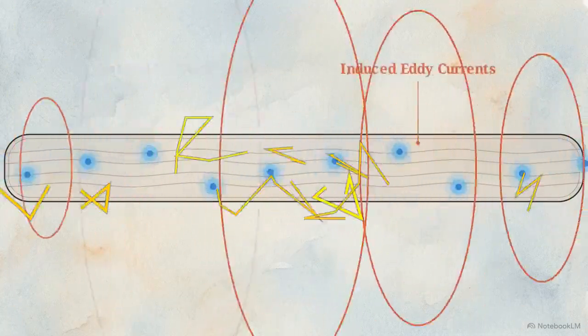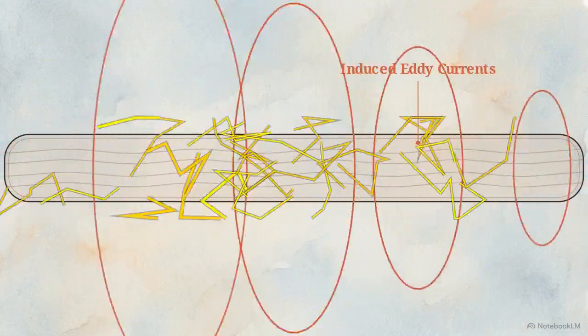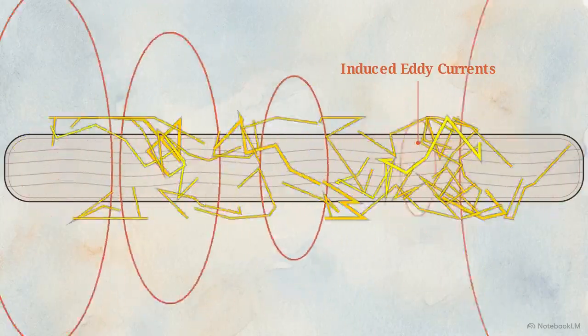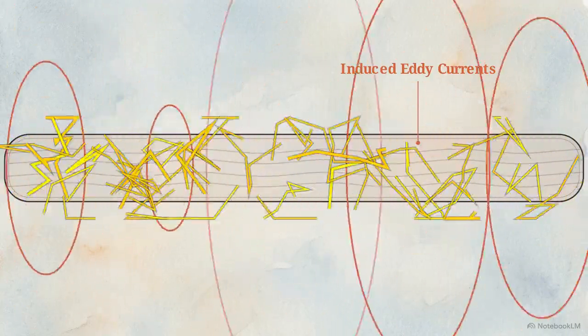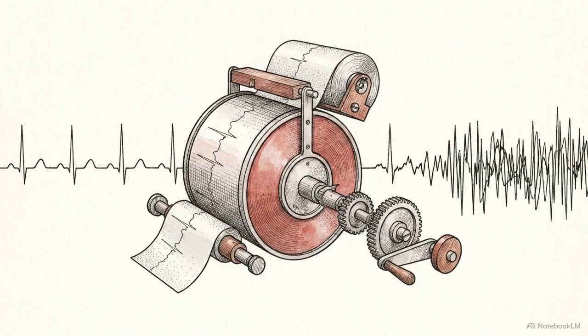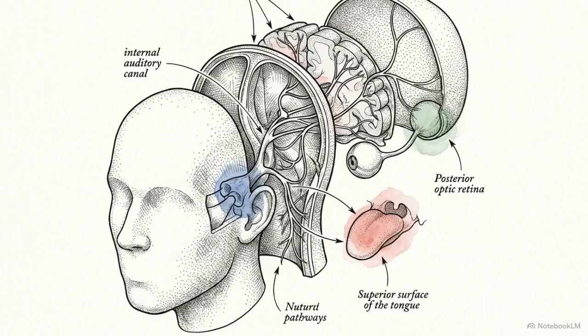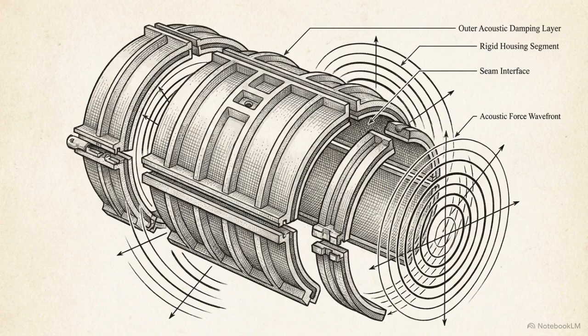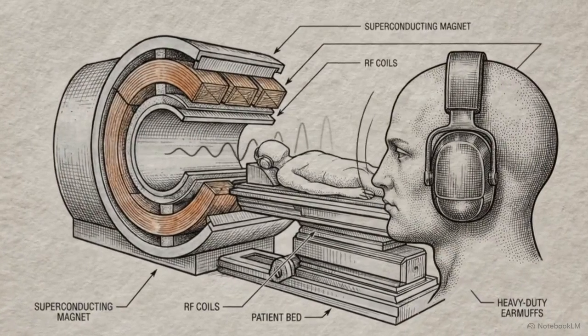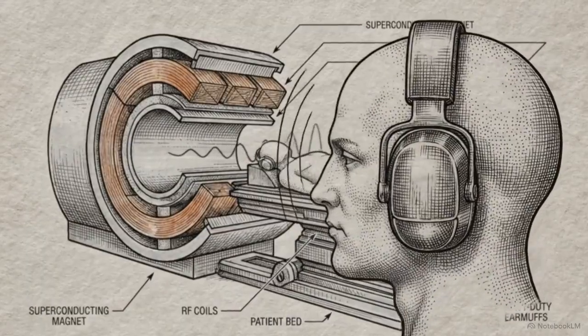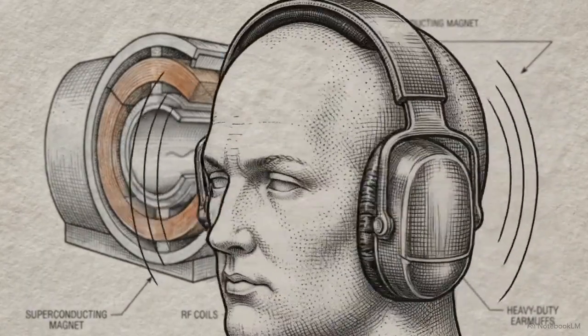As seen here, these induced voltages can override natural nerve signals, leading to peripheral nerve stimulation and involuntary muscle contractions. If these induced currents reach extreme levels, they carry the theoretical risk of causing ventricular fibrillation. Above 3 Tesla, these gradients can cause vertigo, metallic tastes, or flashes of light on the retina by stimulating sensory nerves. The mechanical forces generated by these fast-switching fields also create significant acoustic noise. Scanners are capped at 140 decibels, and hearing protection is mandatory at 90 decibels to prevent permanent auditory damage.